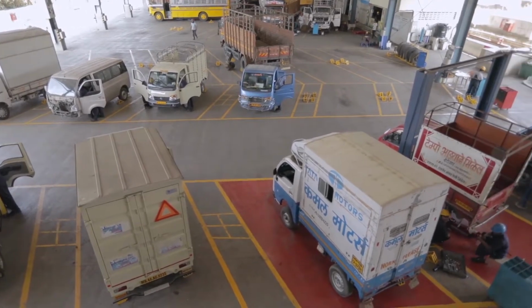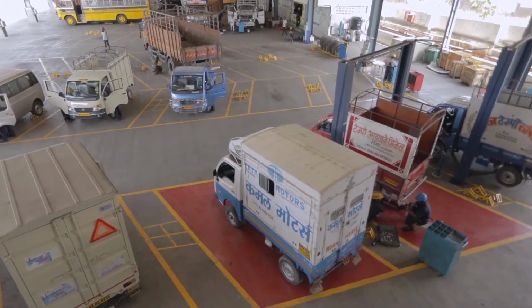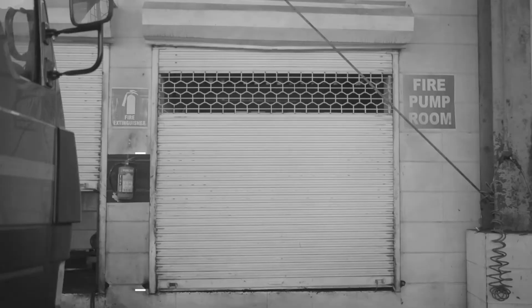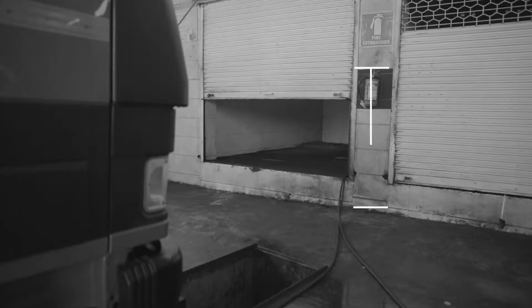Make a site map showing locations of fire extinguishers. The carrying handle of a portable fire extinguisher with a total gross mass of 4 kg and above should be sited approximately 1 meter from the floor. The carrying handle of a portable fire extinguisher with a total gross mass of less than 4 kg should be sited at 1.5 meters from the floor.